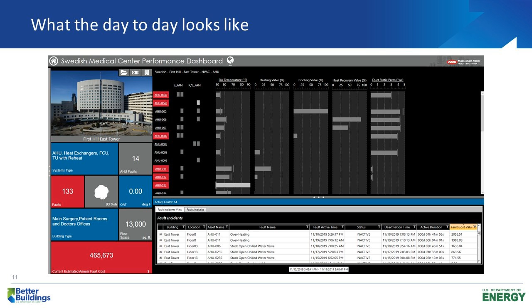Within each incident, we provide details about the fault algorithm in plain text as well as in Excel-style code, so they can better determine the actual problem. We also show the value of the data points at the time the fault occurred, and allow comments on those incidents. They can flag them as acknowledged, perform the corrective action, then return to these pieces of equipment in the Iconics platform and mark them as resolved to track the work accomplished.